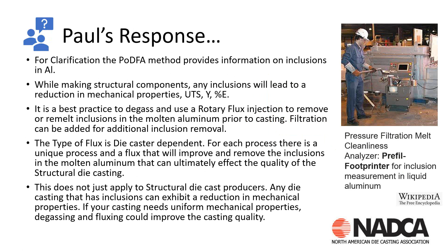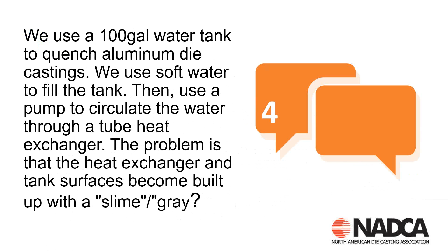The next question is, we use a 100-gallon water tank to quench aluminum die castings. We use soft water to fill the tank, and we use a pump to circulate the water through a tube heat exchanger. The problem is the heat exchanger and tank surfaces become built up with a slime, a gray material, on the areas that come in contact with the quench water. The heat exchanger will clog up and reduce the circulation and flow, causing the water temperature to rise and increase unplanned downtime to clean the system. What is the best practice to reduce downtime and the excessive temperatures?